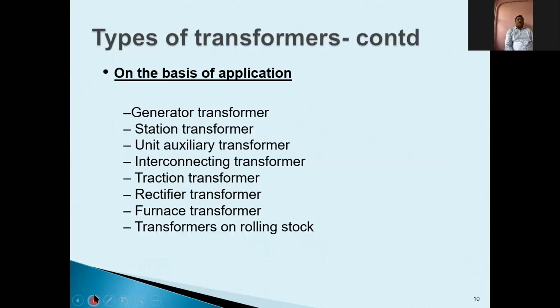Now, based upon the application, again, there are different types of transformers. I have listed a few of them. I could not list all these application-based types of the transformer. You might have heard generator transformer, station transformer, unit auxiliary transformer, interconnecting transformer, traction transformer, rectifier transformer, furnace transformer. So what do they depend on, or what is the difference in manufacturing? Yes, they have differences. Generator transformer will have some different design criteria than rectifier transformer. Furnace transformer will have some different design criteria than your station transformer. So that's why they are categorized as per their application.